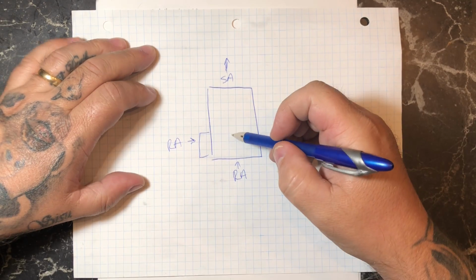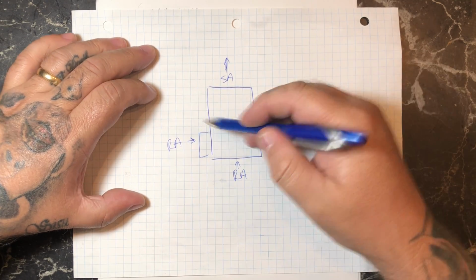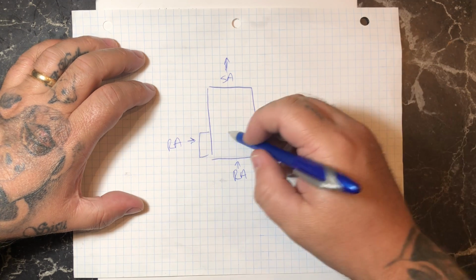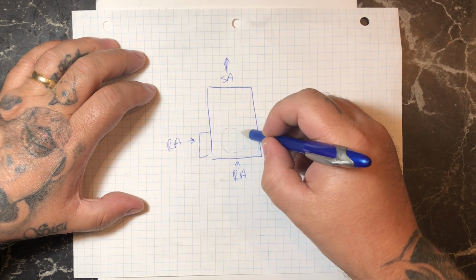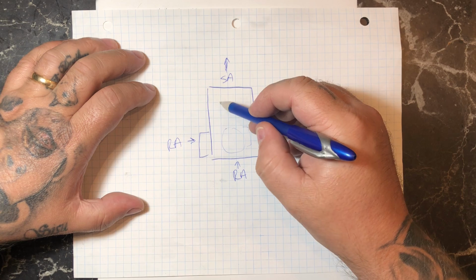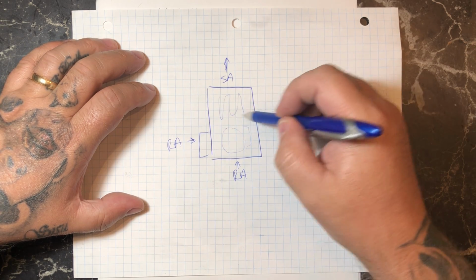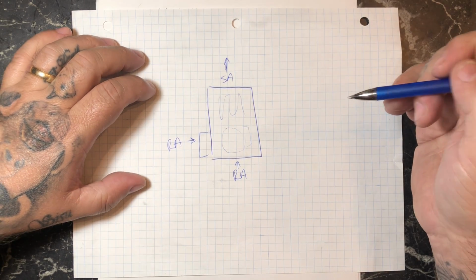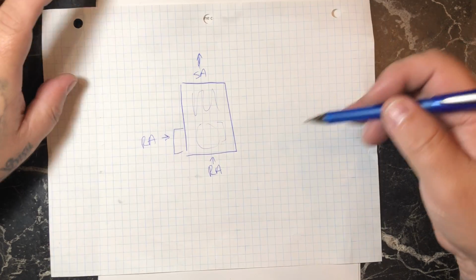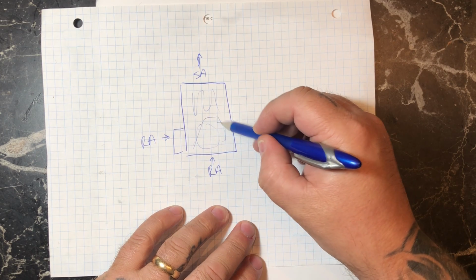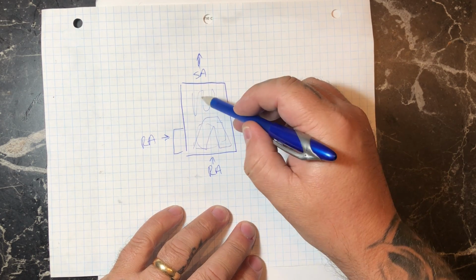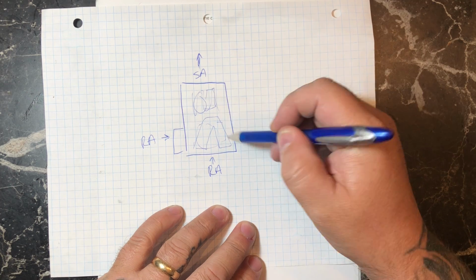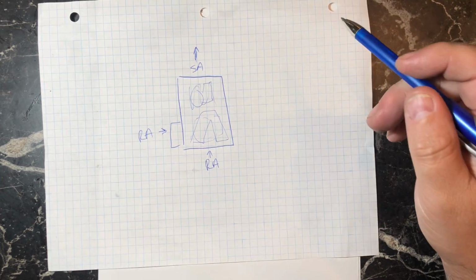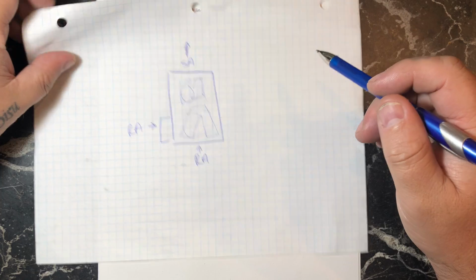So if this is a typical gas-fired furnace or electric furnace or something like that, the fan sits at the bottom, and if it's a gas furnace, the heat exchanger is going to be right above the fan. If it's an air handler for a heat pump, quite often the A coil that's built into the unit will actually be on the bottom, and the blower will be at the top. So the heat exchange happens down below the fan. So it's kind of a loaded question. They don't give enough information to really give an accurate answer on that one.